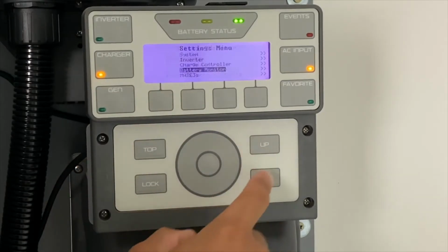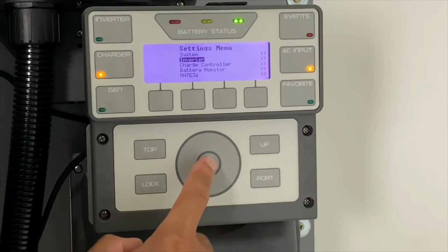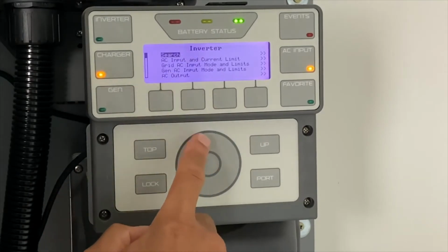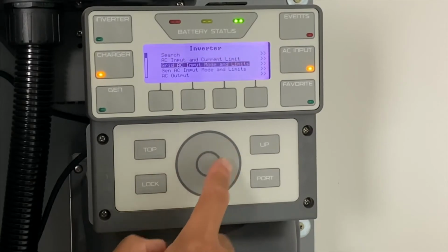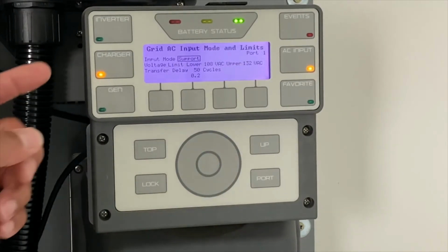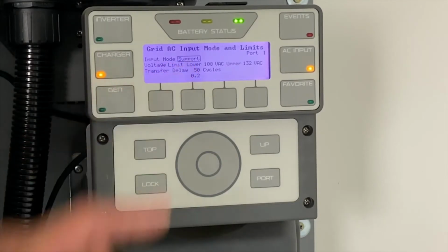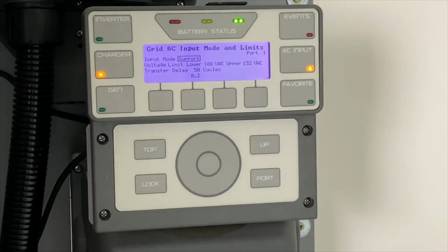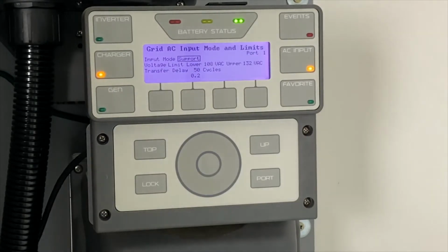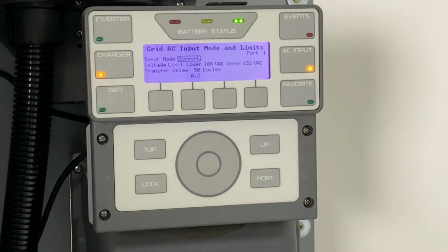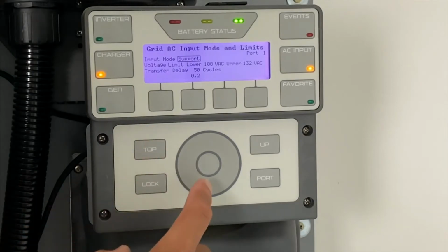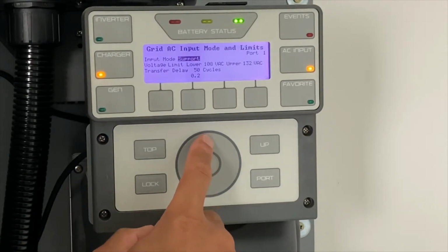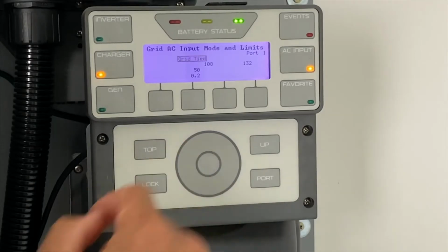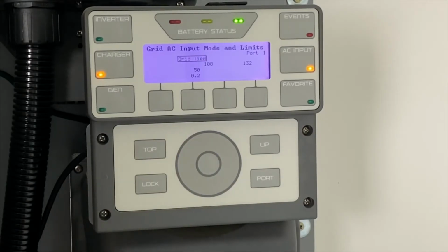Once we've verified that, we go to inverter settings, and we're looking for the grid AC input mode. By default, when the system is first commissioned, it'll be in either support mode or backup mode, meaning solar power keeps the batteries charged and helps provide backup power to the house, but there's no excess sellback. So we change the input mode from support to grid tied, and that allows the unit to connect to the grid and start selling back.